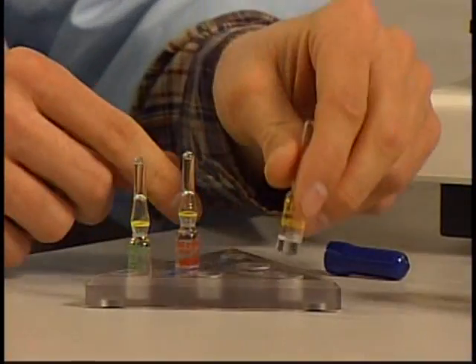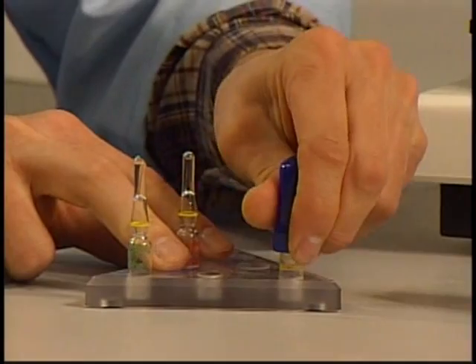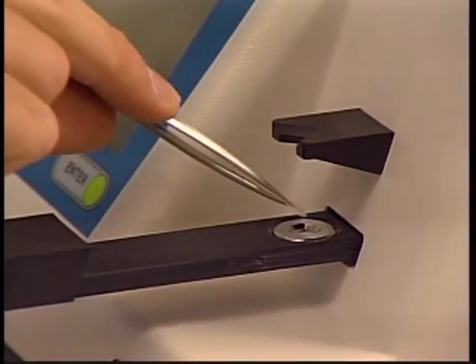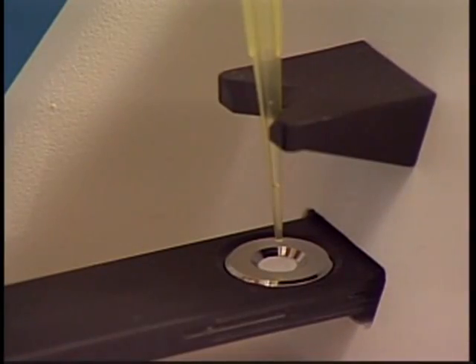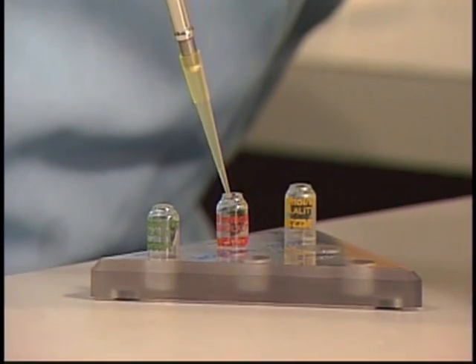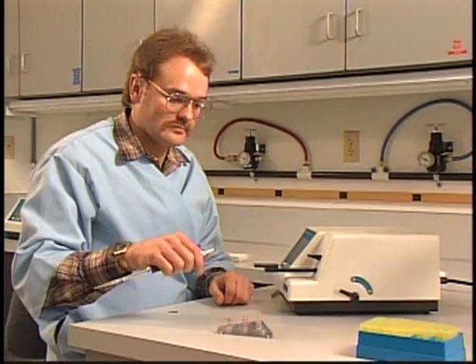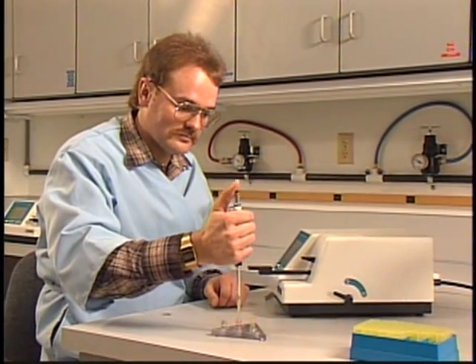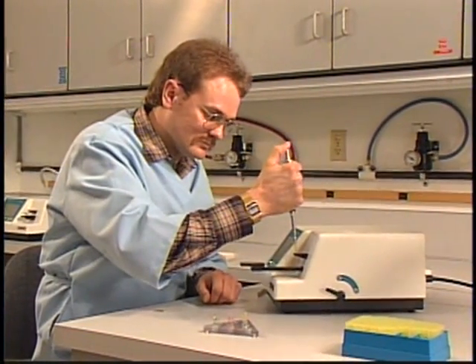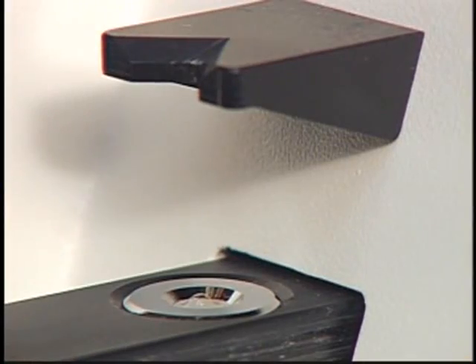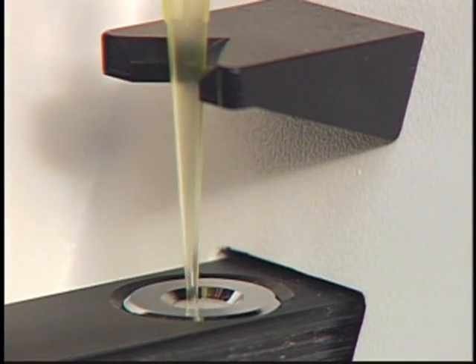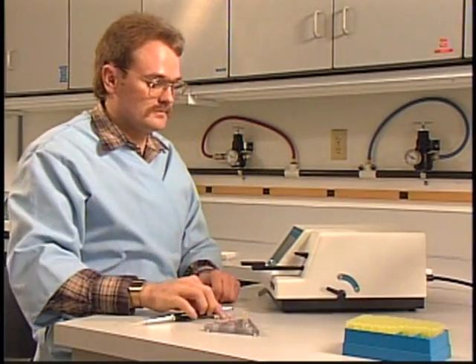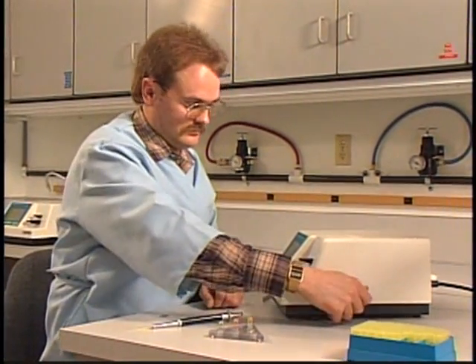You should be able to run at least 100 samples between cleanings, depending on the type of samples you run and your loading technique. If you don't load the osmometer properly, you can contaminate it with one shot. Use proper pipetting techniques and be sure your sample volume is normal. If you're using the correct type of pipette and good technique, you'll rarely see a bubble in the specimen. But if you do, be sure to break it before closing the slide. A bubble burst inside the chamber will contaminate the thermocouple.